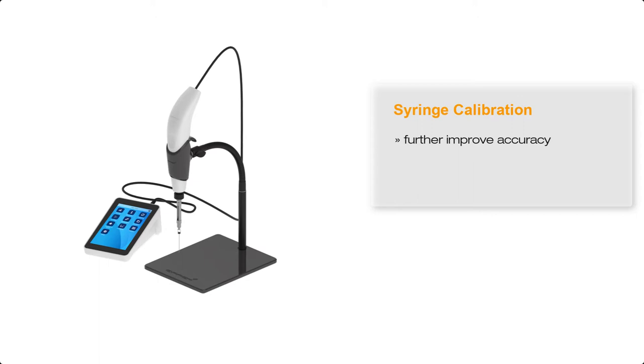But from hundreds of tests on our syringes, we have found that the accuracy in an uncalibrated syringe is much tighter than this. Nonetheless, by calibrating the syringe, the accuracy will often improve to less than 0.2%.